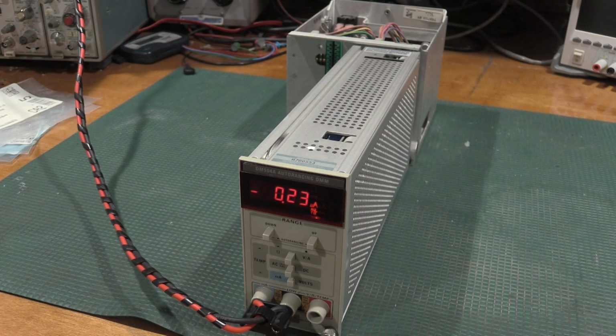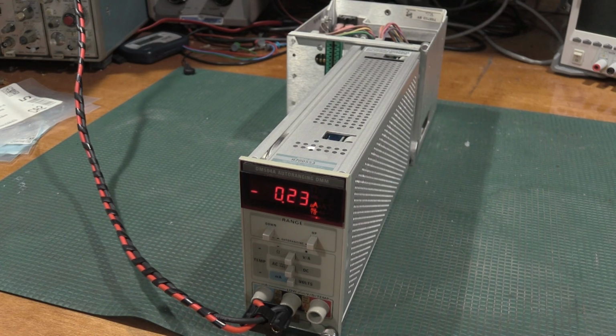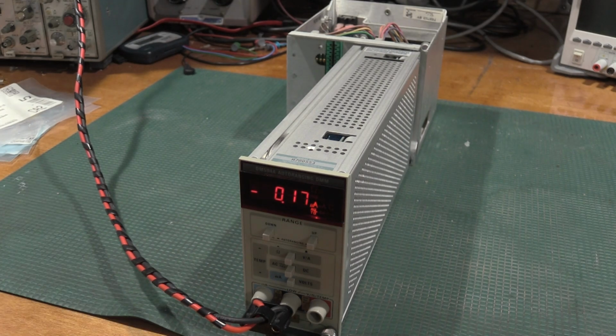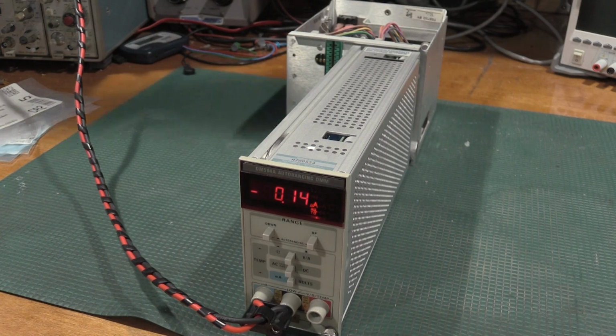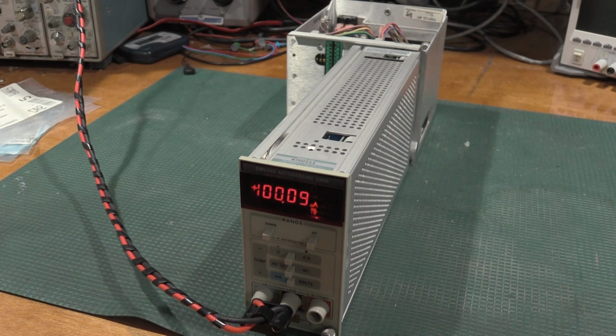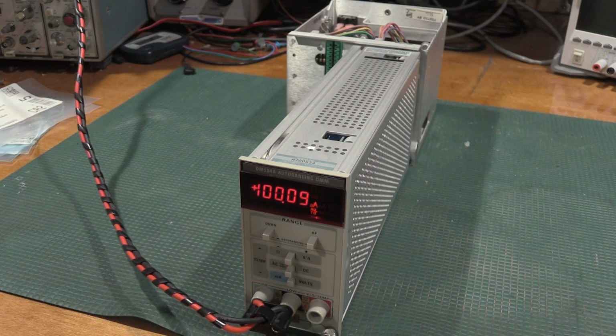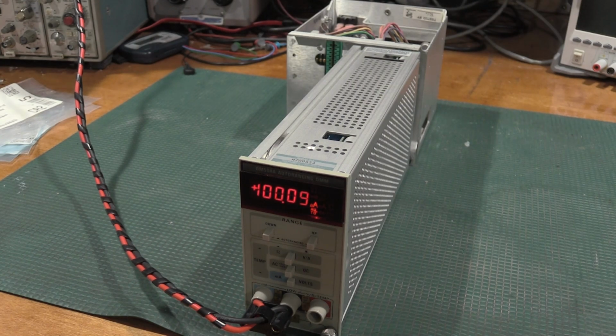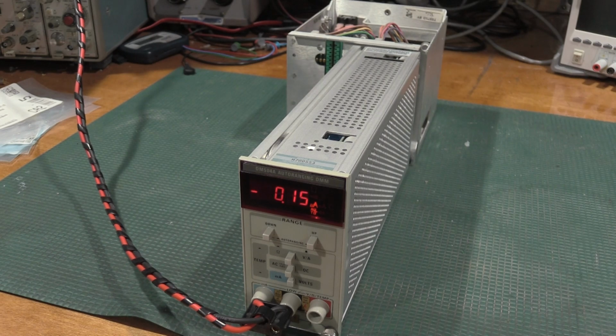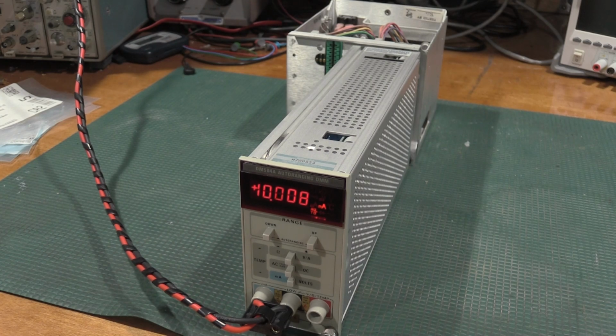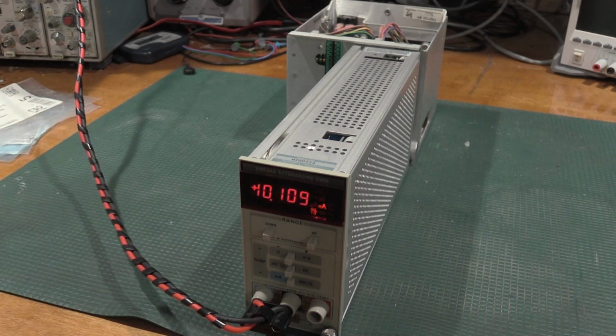All right, we've given the SMU some warm-up time, and we'll hit this with 100 microamps. I've got a 10-volt compliance voltage, but we're going to shoot it with 100 microamps DC. See how we do. It looks pretty good to me. We have a burden voltage on this meter of about 100 millivolts, at least at 100 microamps. Not too bad. We'll see what happens when we turn it up. Let's go to 10 milliamps. That looks good. And I can dial an amperage, so I can even do 10.1 milliamp. Yep. Everything's looking good.